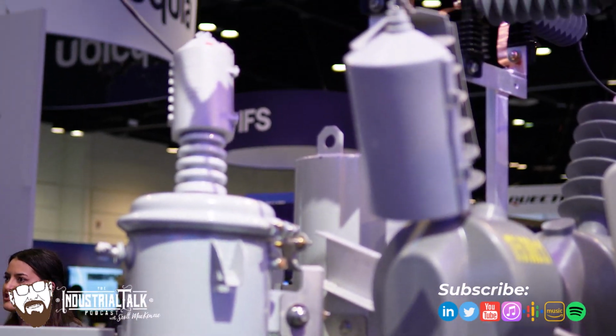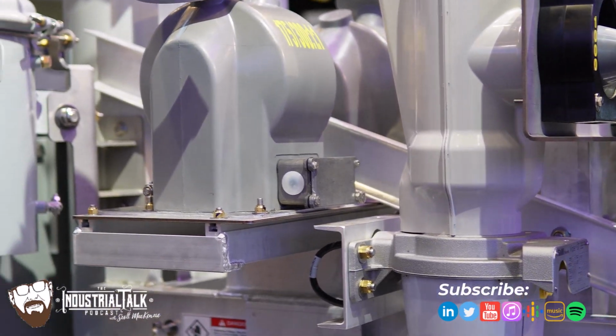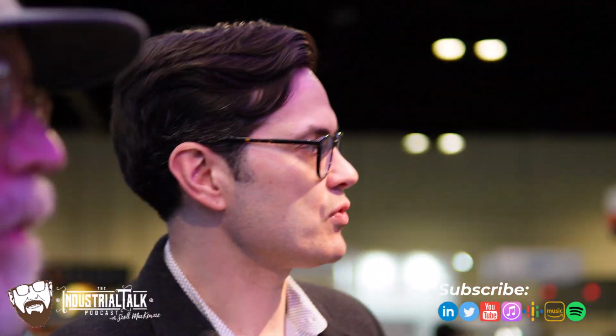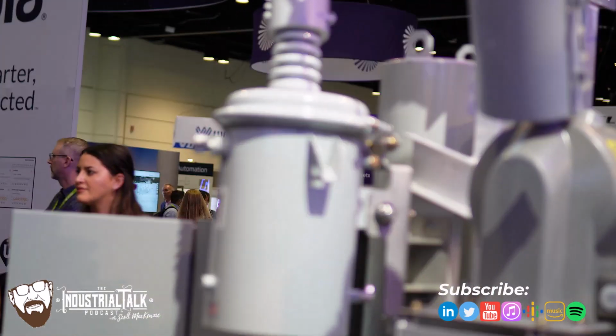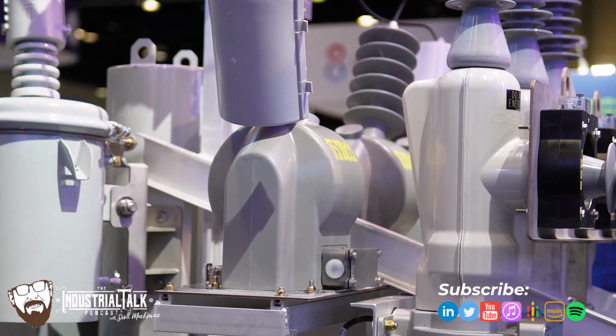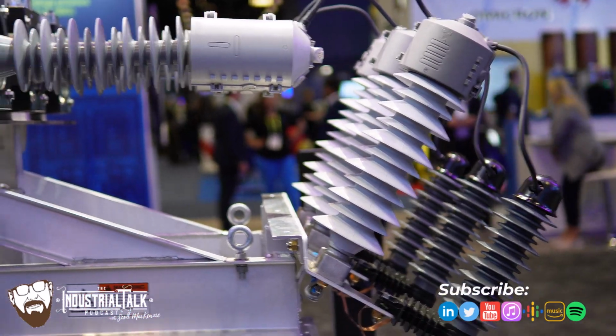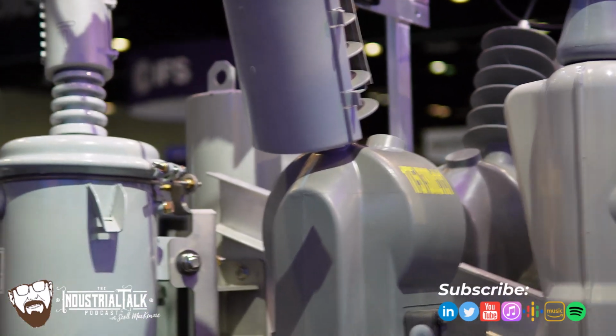Example. So, the G&W recloser, traditionally solid dielectric module, vacuum interruption. It's paired with an industry-leading Schweitzer 651R2, really well-known technology in the industry. Powered by 2 oil PTs for control power. Everyone understands that. But you know what? For a lot of applications, particularly, and this one's designed more as a point of common coupling for a renewable application where I want to do primary metering. Okay. So this isn't necessarily what the utility is using to bill you, but it's what the utility is using to understand how much energy is going back and forth between the renewable and the grid itself.